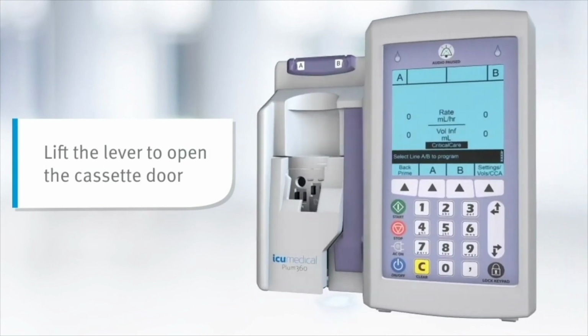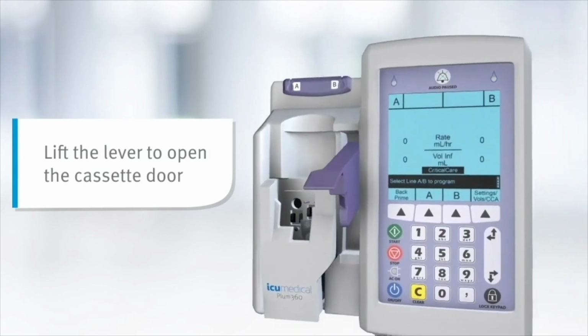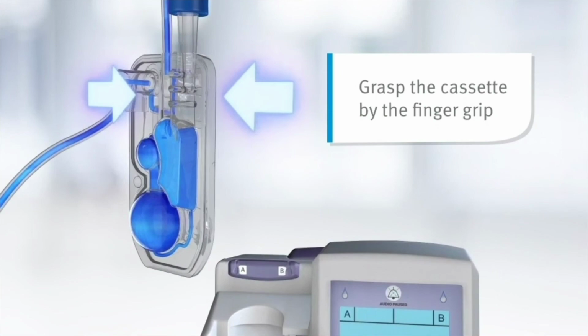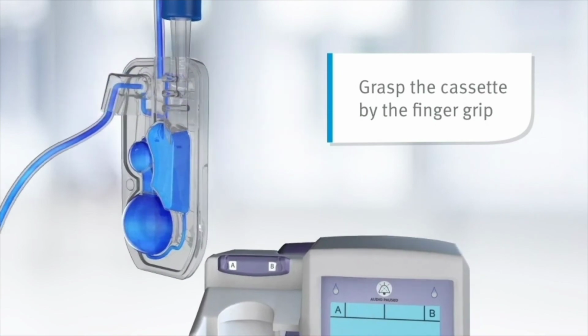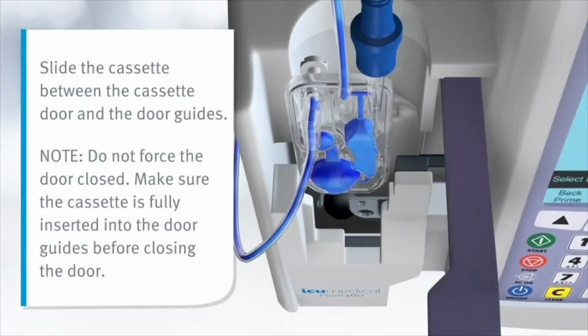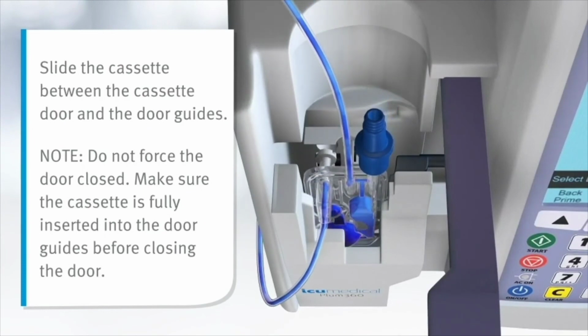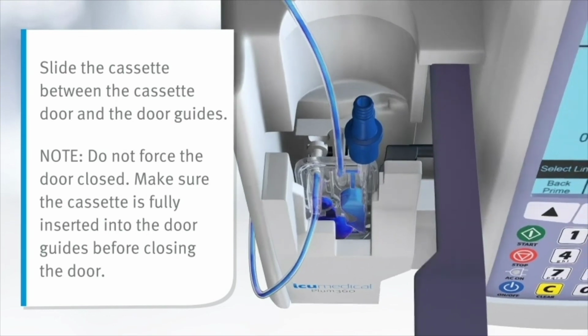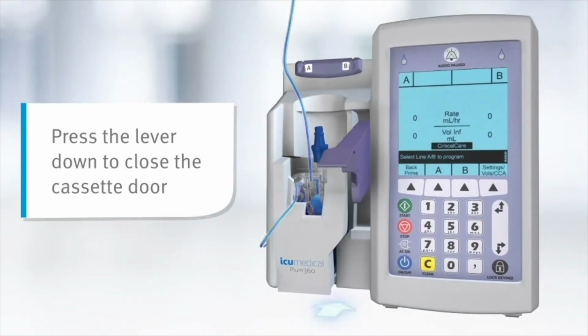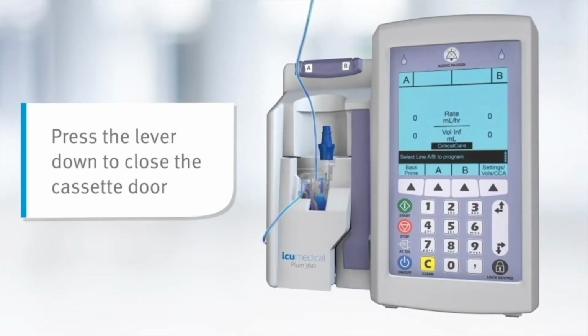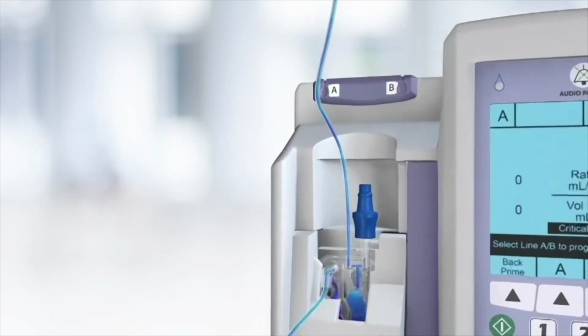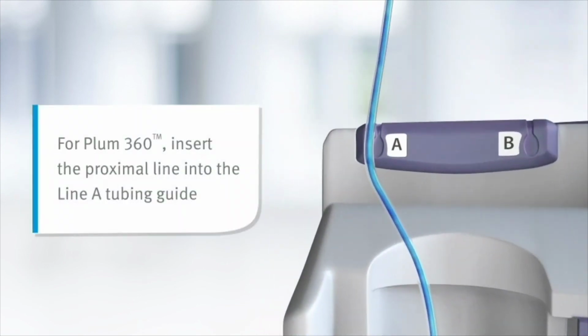Lift the lever to open the cassette door. Grasp the cassette by the finger grip. Slide the cassette between the cassette door and the door guides. Note, do not force the door closed. Make sure the cassette is fully inserted into the door guides. Press the lever down to close the cassette door. For Plum 360, insert the proximal line into the Line A tubing guide.